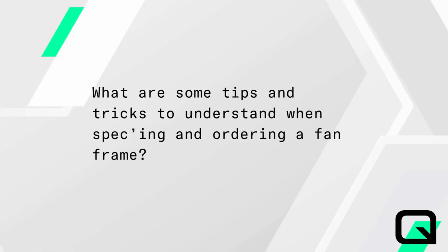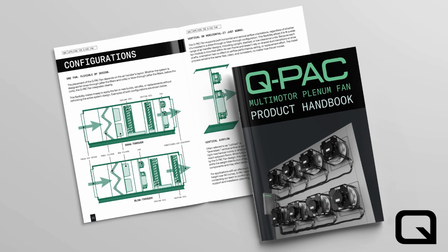To wrap things up, what are some tips and tricks to understand when speccing and ordering a fan frame? Well, the most important piece is going to be the sizing. Making sure that you're measuring the internal width and height at the desired installation location is key. Don't assume that the cross section of the air handler stays the same all the way through. You also want to keep in mind the distance to other components in the air handler, like coils or filters that'll be upstream or downstream.